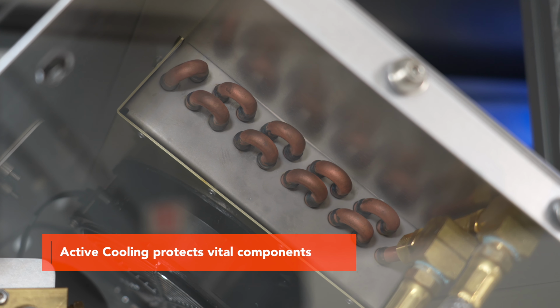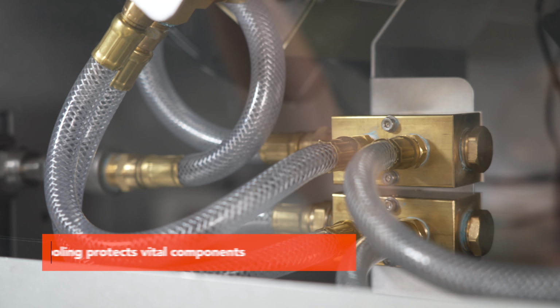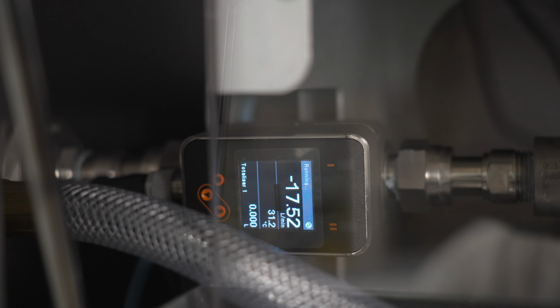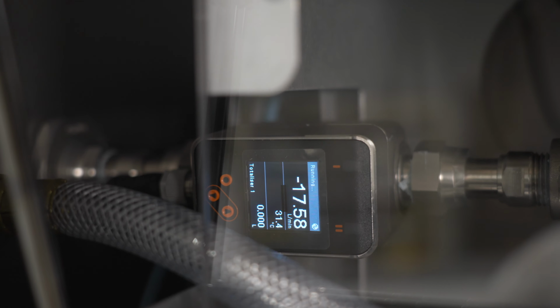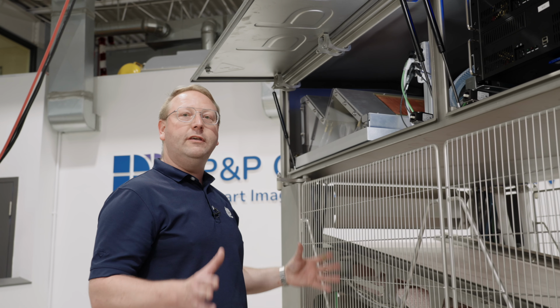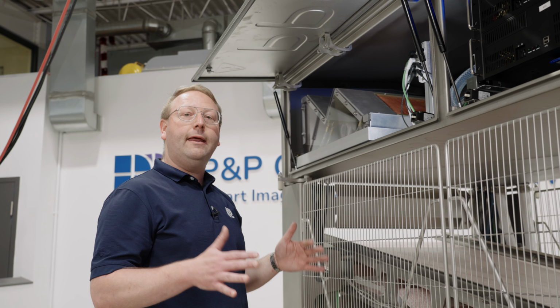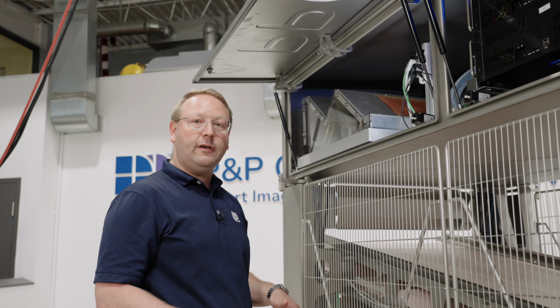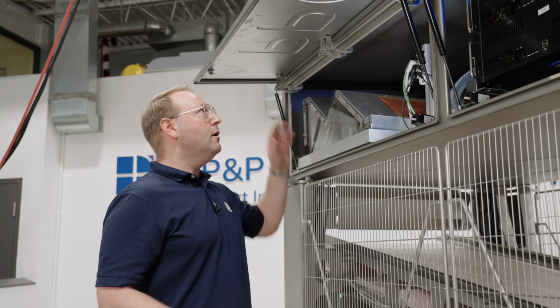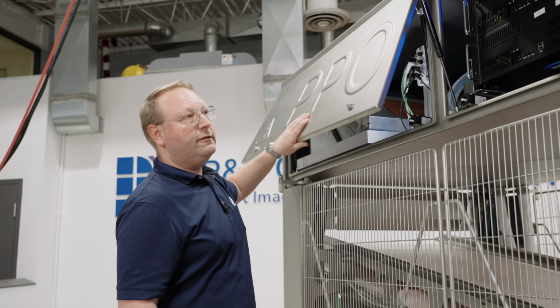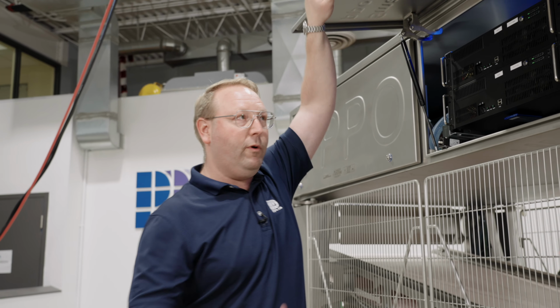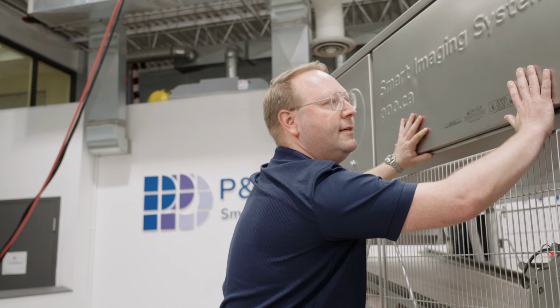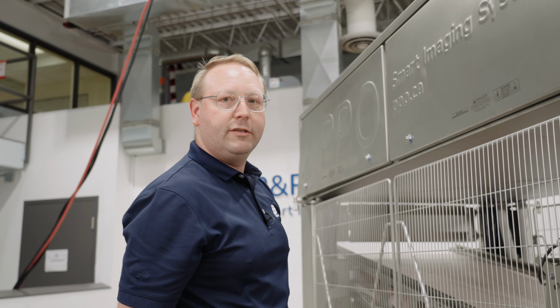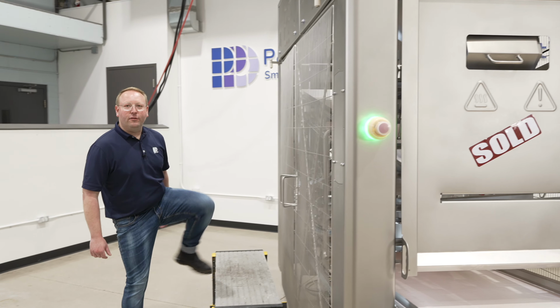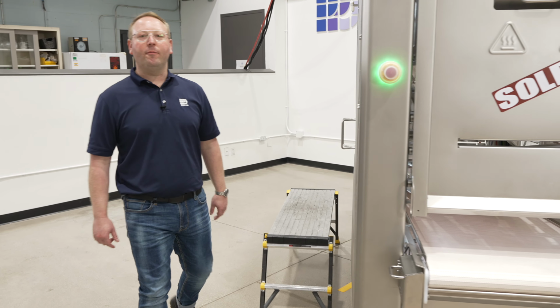On the other side of the cabinet, we have active cooling. There's pumped glycol or water cooled into this heat exchanger, maintaining a nice ambient temperature inside of the control cabinet, inside the detector modules, because all of these components create a lot of heat. We need to manage that heat and manage the temperature inside to ensure optimal performance. The system is sealed, again, like I've said before, with Rittal seals and keys to maintain a watertight environment. Now let's turn the machine on and I'll show you the calibration and operation of the system.